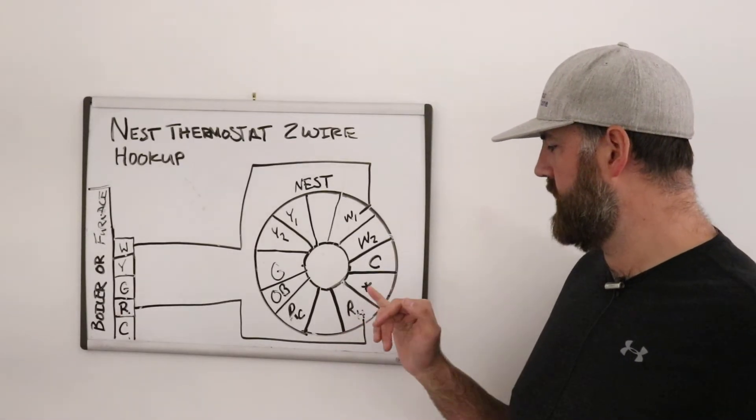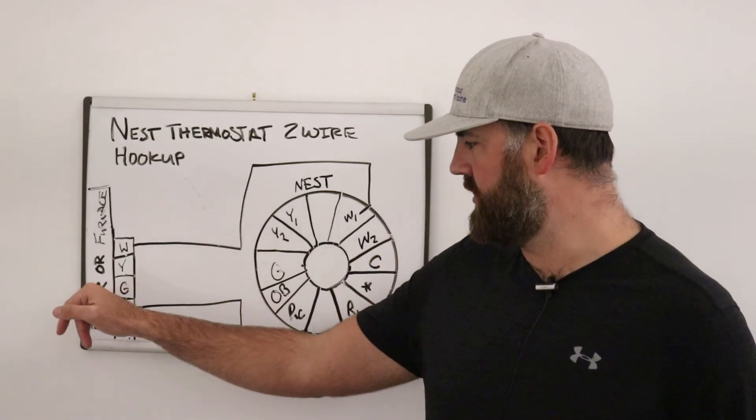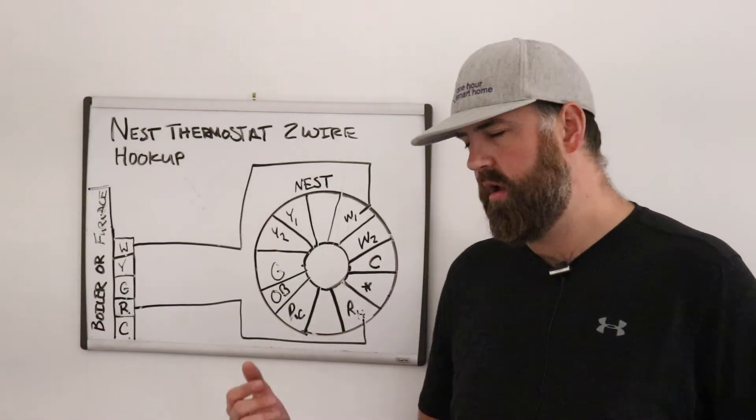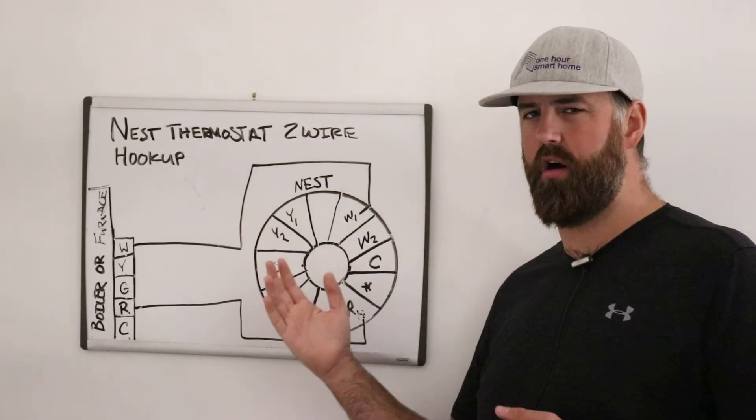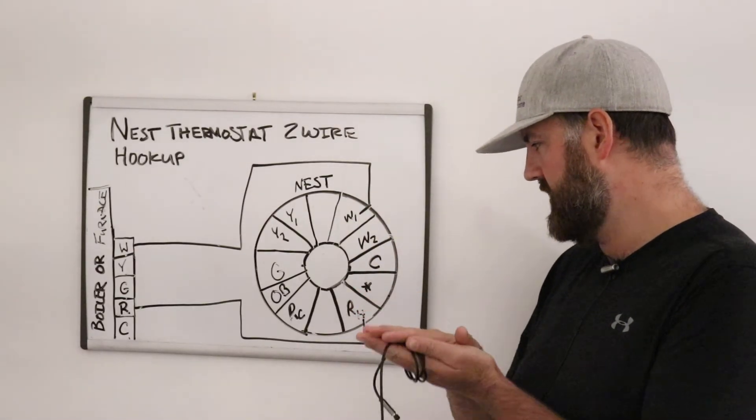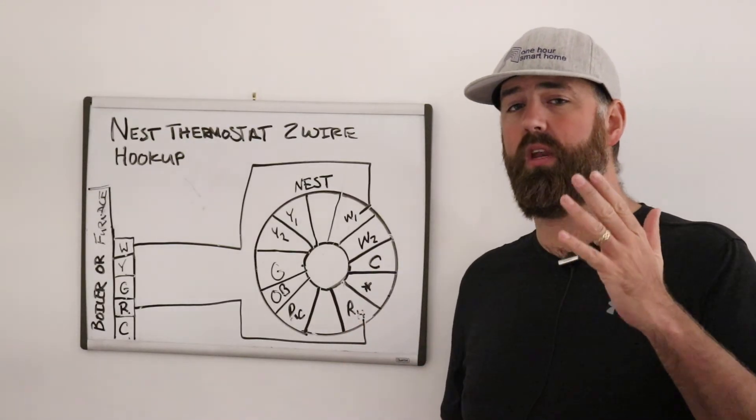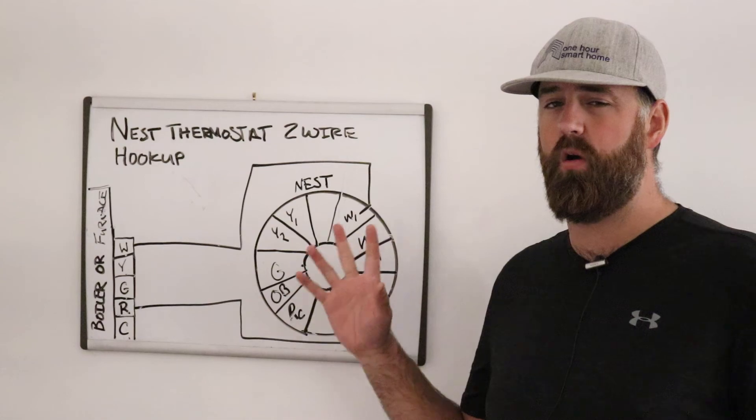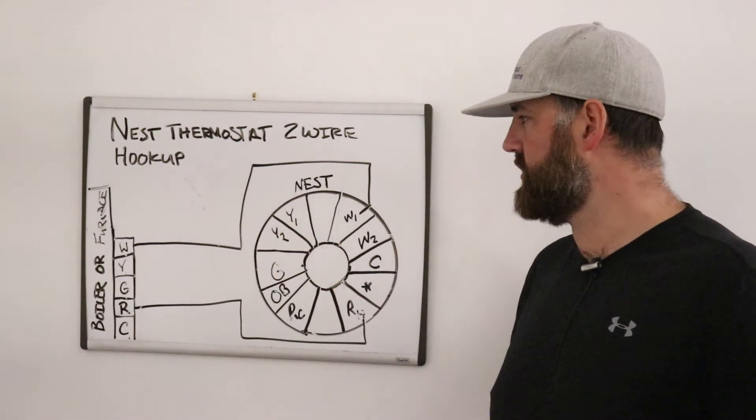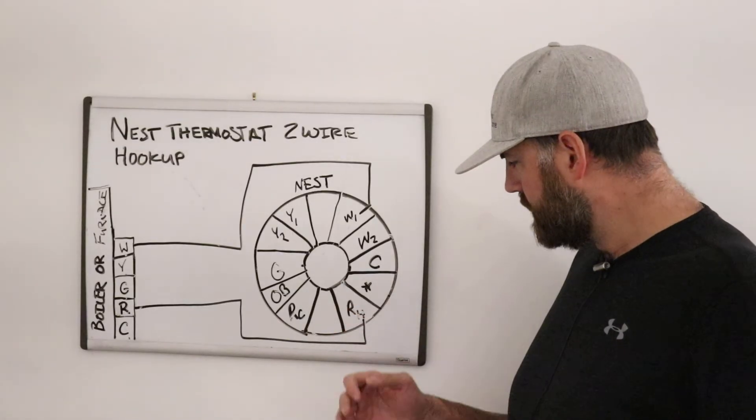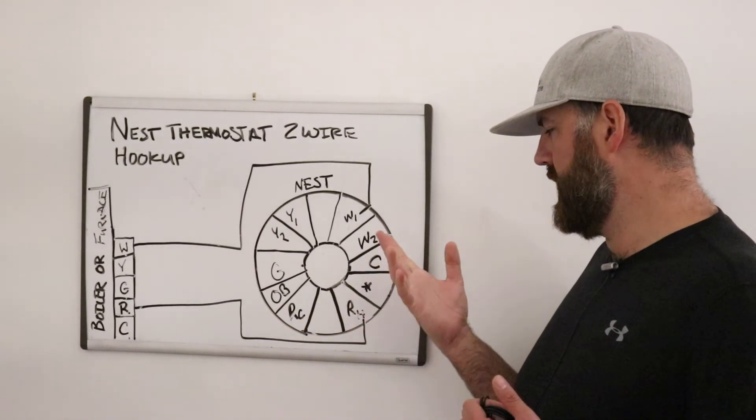In that case, you need a C wire, which allows R to always provide power through the nest into C and back to the neutral on the furnace without causing anything to happen, without the thermostat actually going on or switching down and turning on the heat. It basically just lets the battery charge up on the nest. Most people don't need it. We have a video that shows you how to connect to common wire in another video. You can watch that. Just search common wire installation one hour smart home on YouTube and that will pop up. But for most people, you don't need to worry about that. It's just a neutral wire.